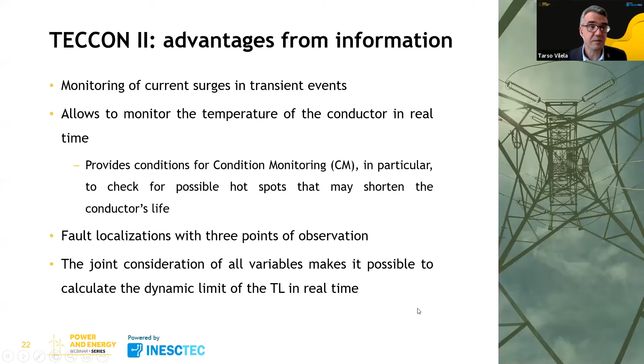It also allows monitoring current surges and the temperature of the conductor, and in this case, it's possible to check for hotspots which may shorten the conductor's life. It allows fault localization with 3-point observation, both substations and the TECCON, or if you have more than one TECCON unit in the line, you may have 4 or 5 points of observation. It also allows us to evaluate the joint consideration of all variables and calculate the dynamic limit of the transmission line in real time.